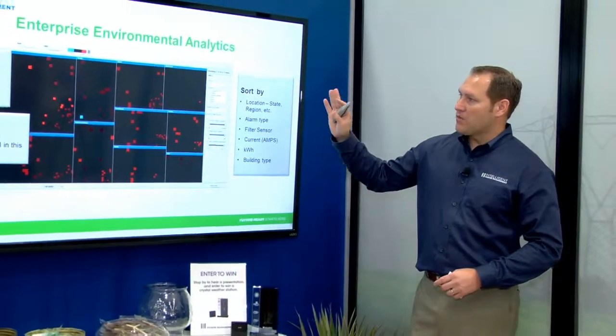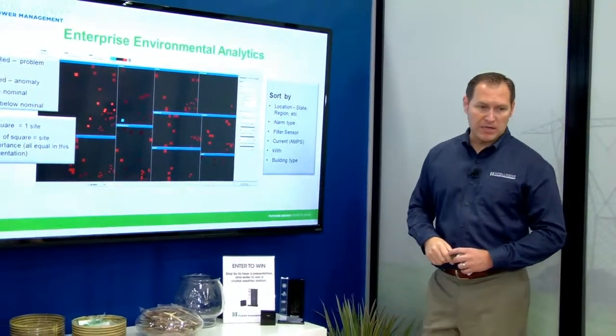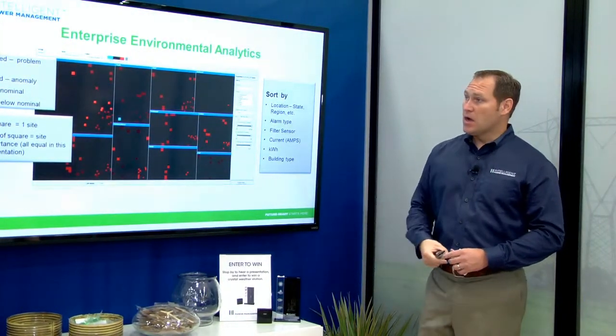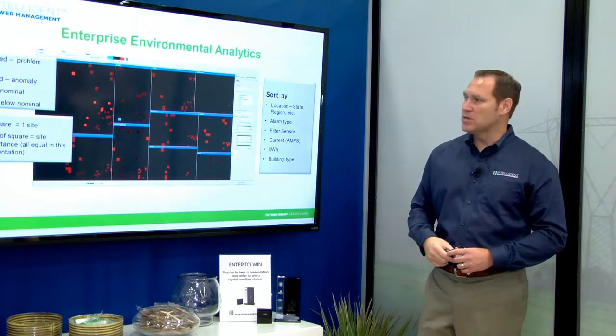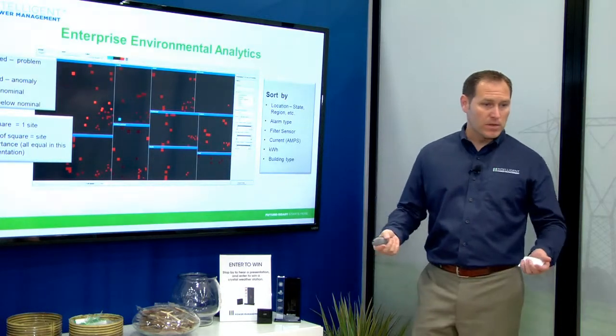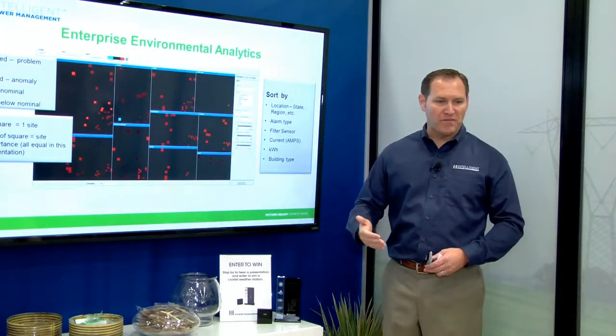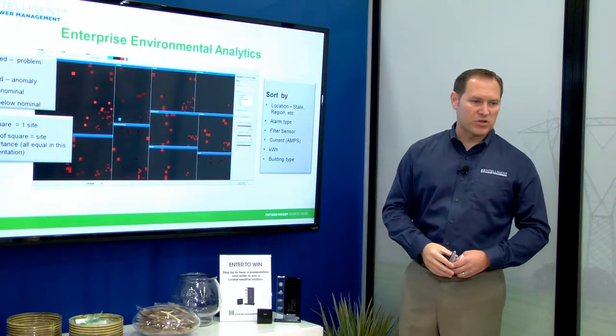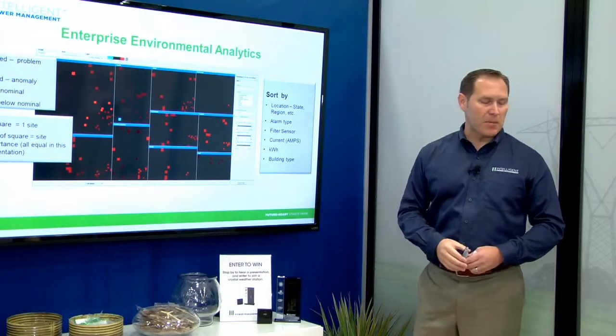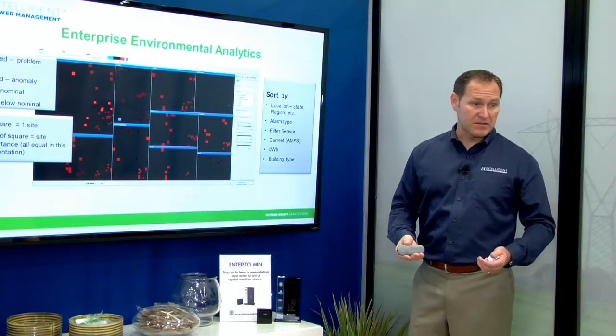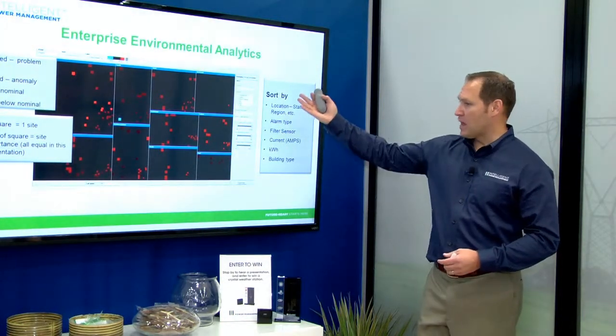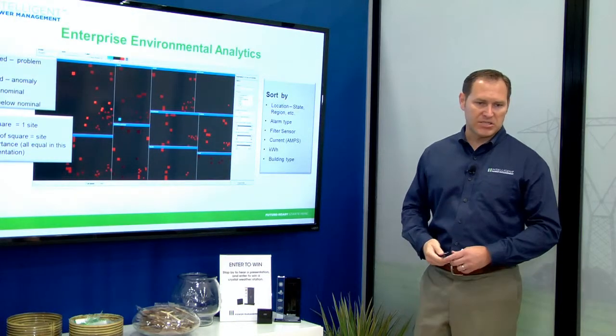We can sort this based on location, region, utility provider, HVAC brand, size, who services that particular site or piece of equipment — it doesn't matter. From a temperature point of view: bright red is a problem site, hotter than it should be; dark red is an anomaly, a little out of operational parameters; black means nominal; and blue means it's too cold. We look at both dark red and blue — blue likely means the air conditioner is overperforming and cooling the site more than it should, costing additional energy. Red probably indicates the HVAC is not performing to operational standards or is defective. We can sort by all these parameters — it's unlimited how we can sort based on the information we collect.